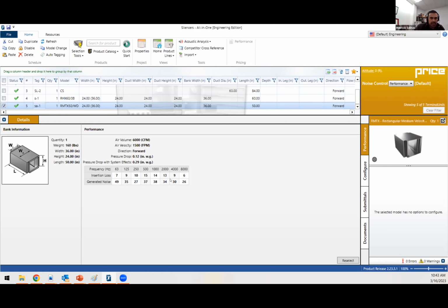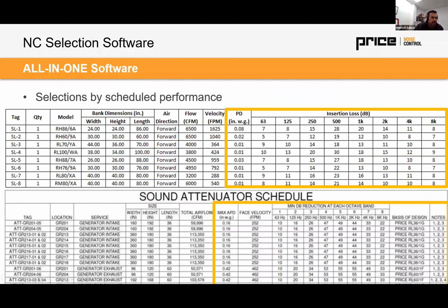In general, the way to think about generated noise, just because we don't have a lot of time to go through several examples, is if the difference between the generated noise of a silencer and the sound power of the unit is 10 decibels or greater, you're not adding noise. Once those numbers are really close, generated noise to the numbers of the fan or a single duct valve, venturi valve, fan coil unit, if those numbers are close, you're probably adding noise to the system. That's why this piece of information is important to you. All right, so it appears that I only have 11 minutes left, so let's pick this up.